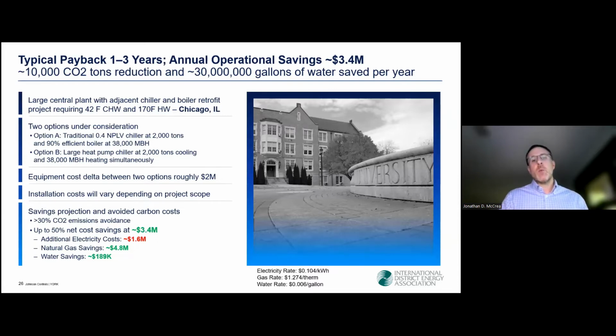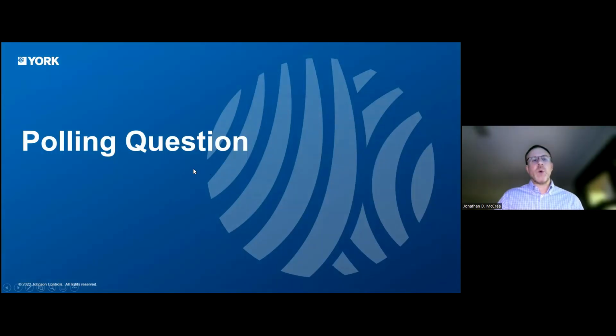And we have scope 1 CO2 emissions reduced of about 10,000 tons per year. So I will say, granted, this is something of an ideal case, and it's a very large machine with favorable utility rates. But it's not uncommon at all to see net savings well north of $1 million. And the paybacks that we're typically seeing, as we've noted, are under 3 years, especially with the natural gas rates where they are today. All right, so I think we're going to roll into a final polling question here.